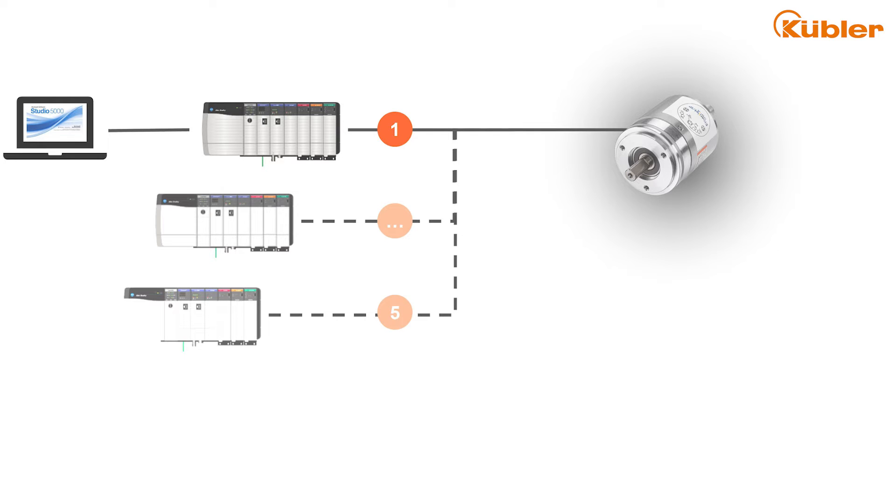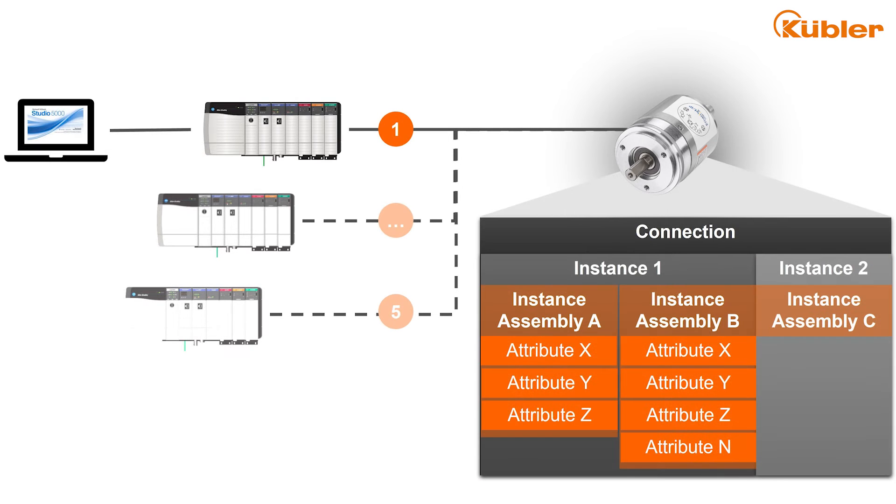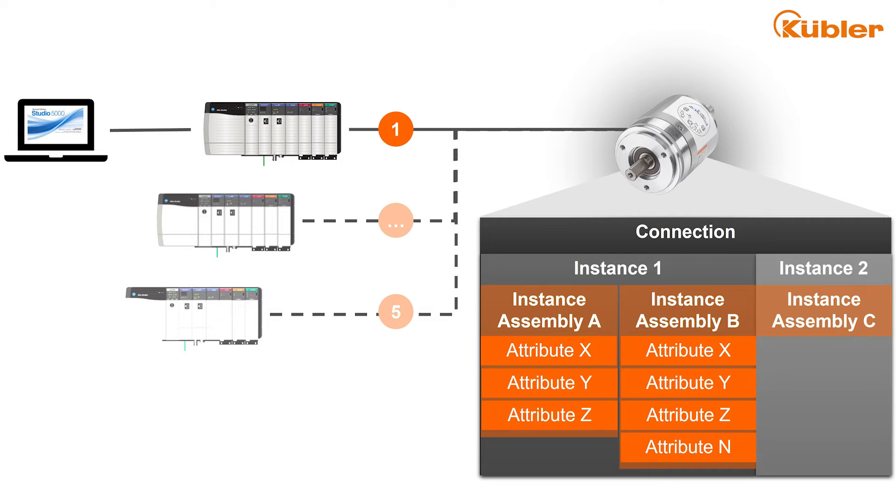Next, the encoder has to be added to the network and the connection has to be configured. The F58 Ethernet IP can have up to five PLC connections. In simple terms, a connection defines what kind of data is transferred between the encoder and the PLC. The encoder has one instance containing multiple instance assemblies. Instance assemblies, in turn, consist of multiple attributes. Depending on the type of application you have, it may make sense to use other connection types than the default connection.